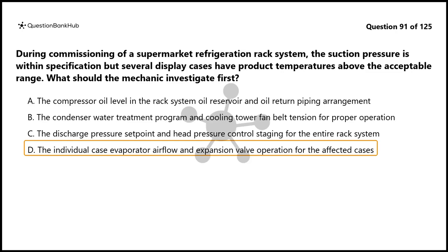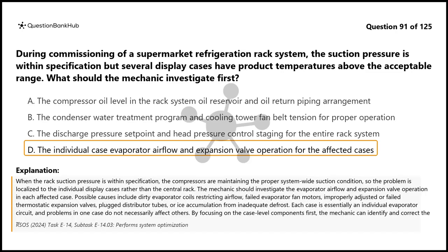The correct answer is D. When the rack suction pressure is within specification, the compressors are maintaining the proper system-wide suction condition, so the problem is localized to the individual display cases rather than the central rack. The mechanic should investigate the evaporator airflow and expansion valve operation in each affected case.